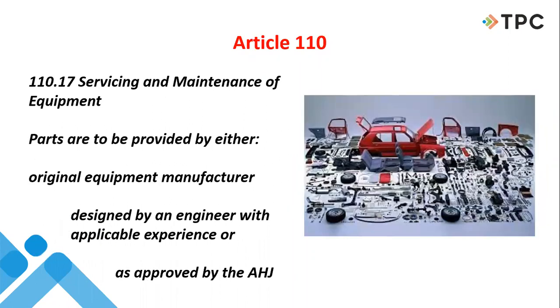What they're talking about, replacement repair parts, are to be provided by either original equipment manufacturers, individually designed by engineers with the applicable experience and knowledge, or in certain situations, approved by the AHJ, by the inspector. And that isn't always as cut and dried as is often thought of. The AHJ may or may not be all that knowledgeable within the scope of certain repair parts, replacement parts, engineering level, structural level type things.